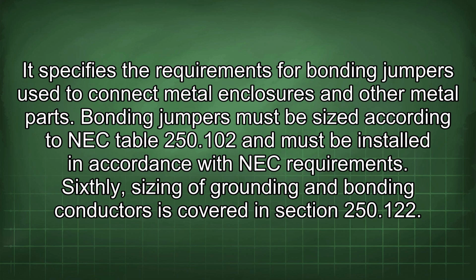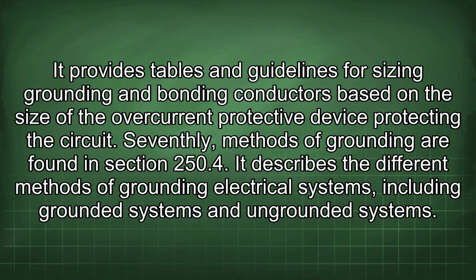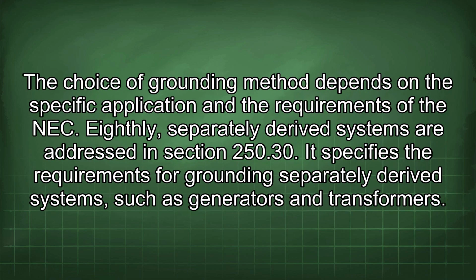Sixthly, sizing of grounding and bonding conductors is covered in Section 250.122. It provides tables and guidelines for sizing grounding and bonding conductors based on the size of the overcurrent protective device protecting the circuit. Seventhly, methods of grounding are found in Section 250.4. It describes the different methods of grounding electrical systems, including grounded systems and ungrounded systems. The choice of grounding method depends on the specific application and the requirements of the NEC.